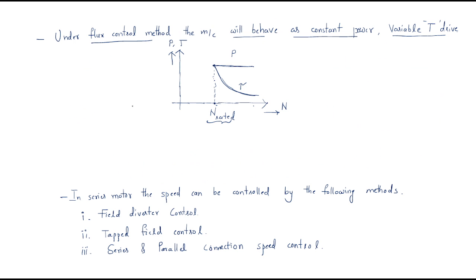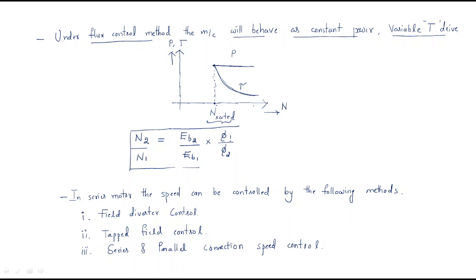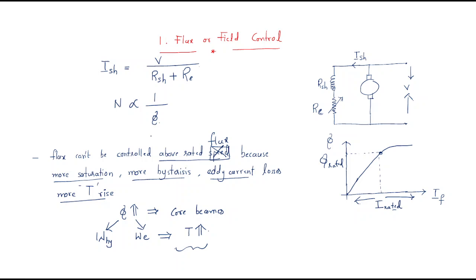We can also derive a speed ratio relation: N2/N1 = (Eb2/φ2) / (Eb1/φ1), which gives the relation between two speeds N1 and N2. This is how speed is controlled by varying the field flux. The most important point is that field flux control is only effective above rated speed values. I hope all of you understood this session — thank you.